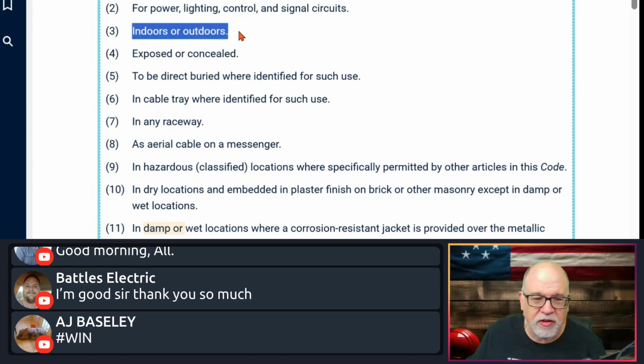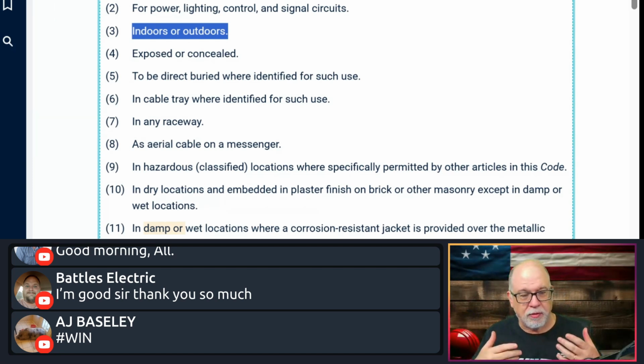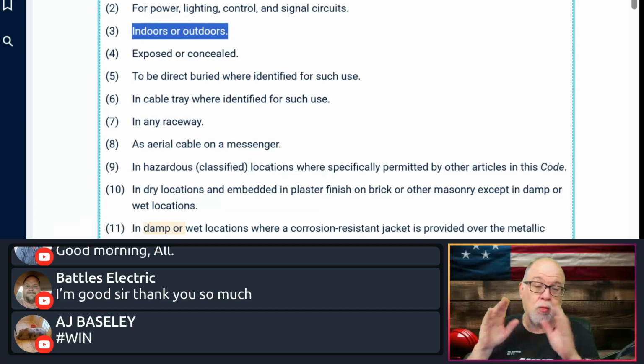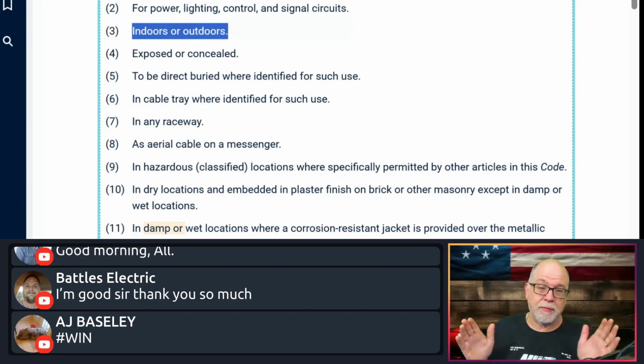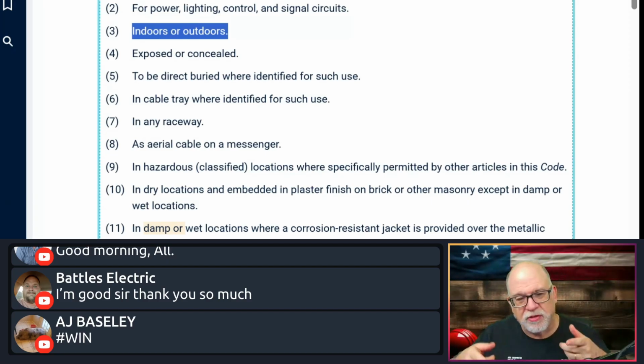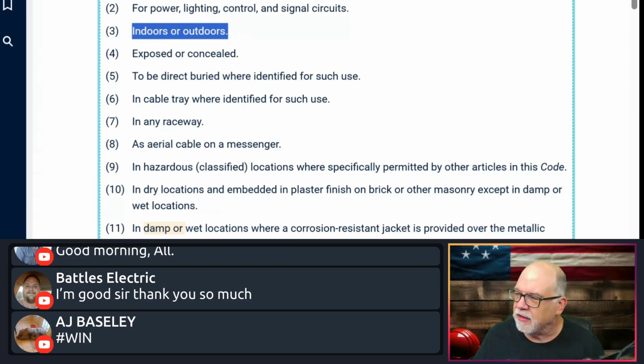It's good for indoors and outdoors. Yes, it is good for outdoors with the caveats, right? That you have to, for example, have the coating on it. Okay. We'll see the other allowances for the smooth and that type of thing. But in general, MC cable can be used indoors and outdoors. Just remember that people read this wrong and say, oh, MC outdoors, just regular MC. No, it can be used outdoors, but there's a caveat. It has to have the covering on it if it's interlocked, for example. So again, you have to understand how to read these things.